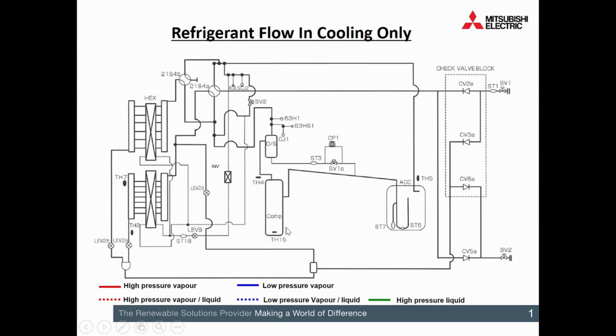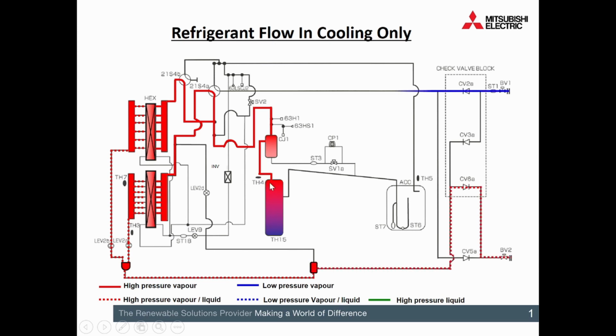So off the top of the compressor, there's TH4, to give you an idea of the actual discharge temperature. Normally somewhere between 50 to 90 degrees. If that TH4 sees temperatures in excess of 115 degrees, we start slowing down the speed of the compressor to look after itself. If it gets to temperatures of 120 degrees, that's when we get an 1102 error kicking up, so it gives you an idea what's going on.